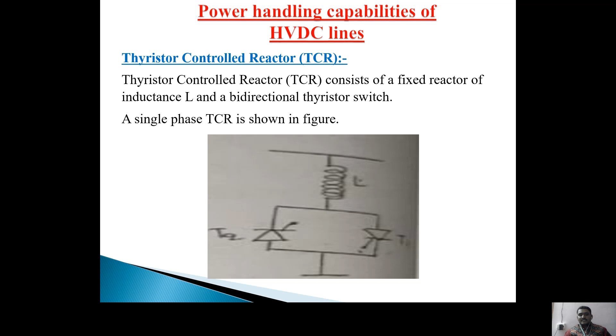The thyristors can block voltage up to 4000 to 9000 volts and conduct currents up to 3000 to 6000 amperes. In a thyristor controlled reactor, the current in the reactor can be controlled from maximum to minimum by firing angle control. When alpha is equal to 0 degrees, the thyristor T1 is closed, that is the switch is closed, at the crest of the applied voltage, and the current flowing through the reactor is the same as the steady state current.